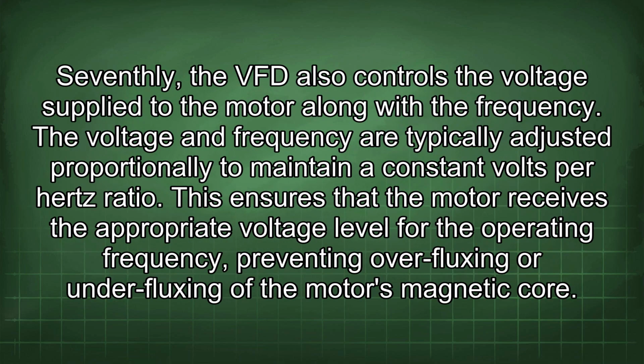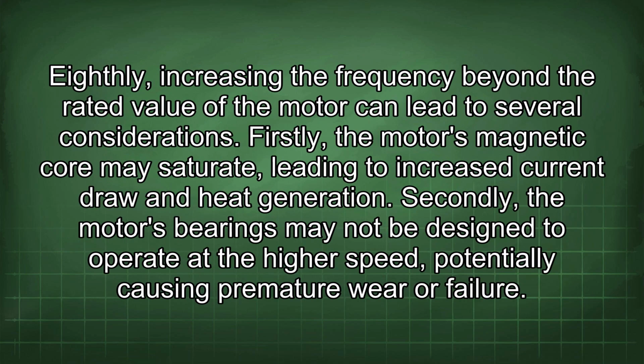Seventhly, the VFD also controls the voltage supplied to the motor along with the frequency. The voltage and frequency are typically adjusted proportionally to maintain a constant volts per Hertz ratio. This ensures that the motor receives the appropriate voltage level for the operating frequency, preventing overfluxing or underfluxing of the motor's magnetic core. Eighthly, increasing the frequency beyond the rated value of the motor can lead to several considerations.